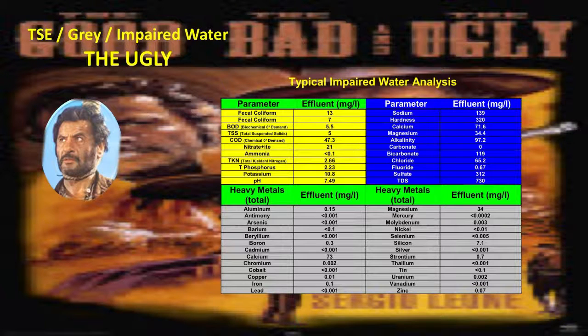The blue is benign, with the exception of the chlorides. The bottom one is every discharge from society imaginable, including radioactive isotopes, etc. But let me stress that in this water analysis, the most corrosive, most injurious chemical is chlorides—salt. It's the number one corrosive agent for heat exchanger tubing.